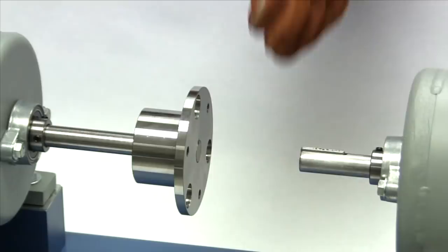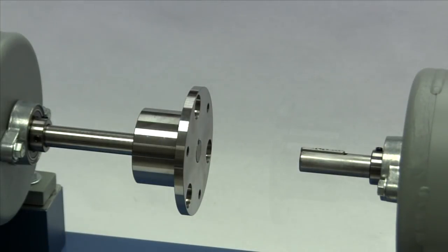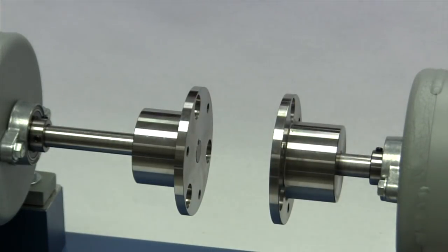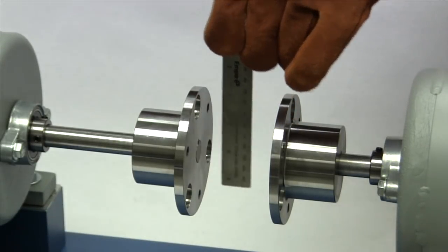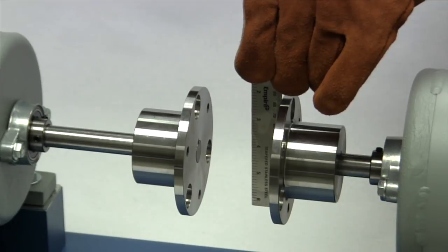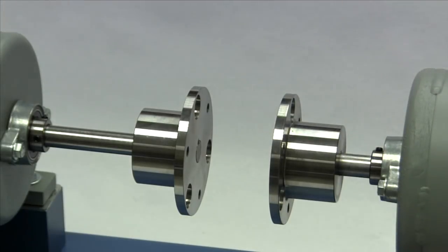Once the hubs cooled down, they could be quite difficult to reposition. When the hubs are in position, the flanged end of the hub should be in line with the end of the shaft and the end of the key. At this time, let the hubs cool to the ambient or room temperature before continuing.